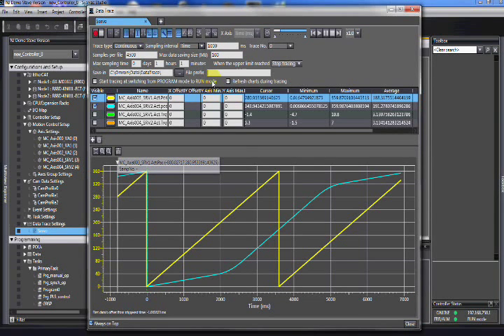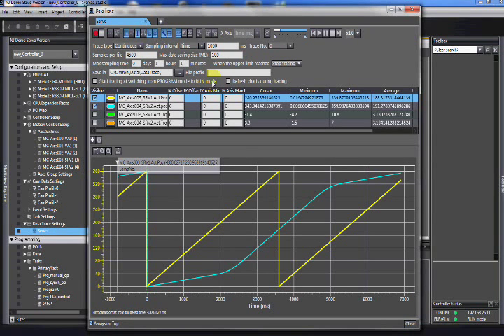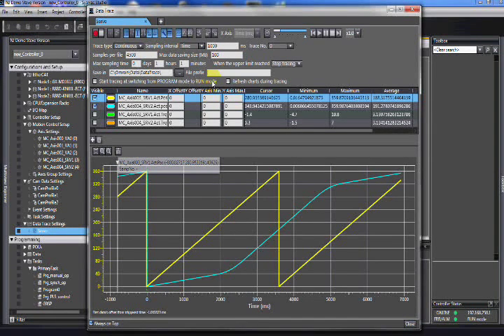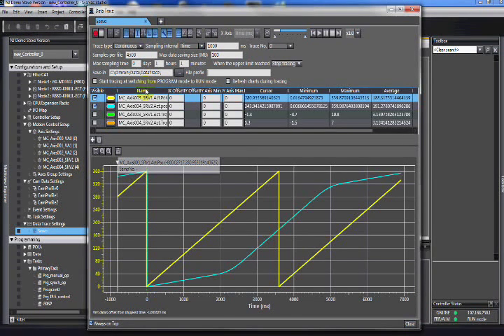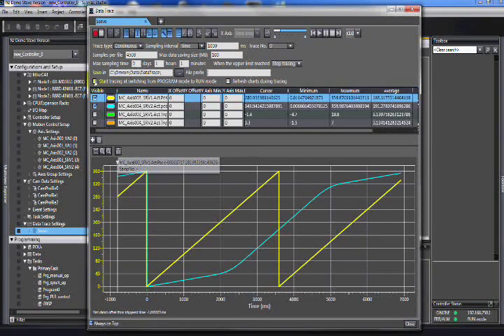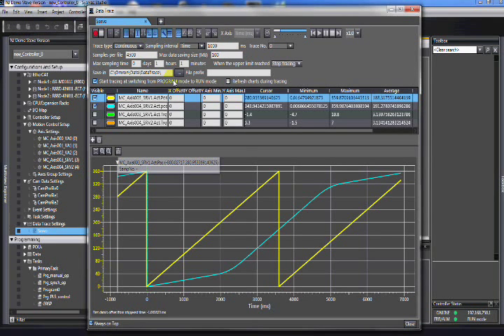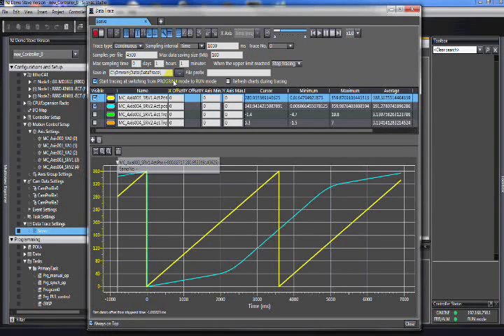You'll notice that the only limit on when it will stop logging, in this case, would be the maximum sampling time, because it just creates new files and keeps going. This one actually seems like a better application for starting tracing when switching from program to run mode. You turn it on, you're looking for something that is, I don't know, overheating something.